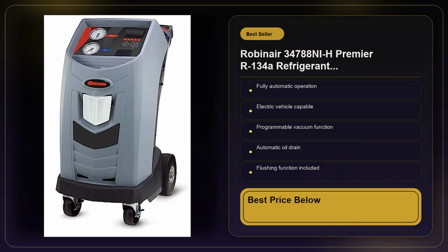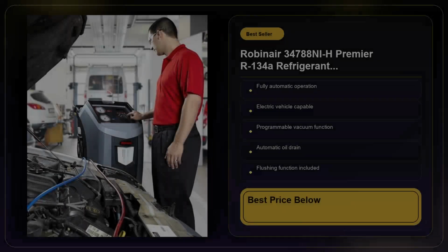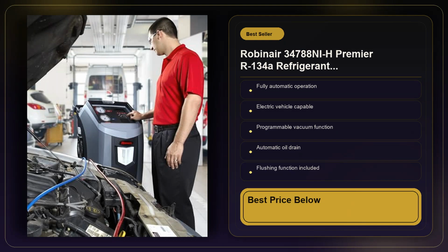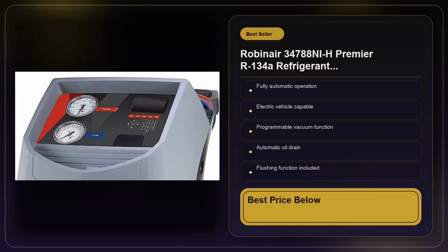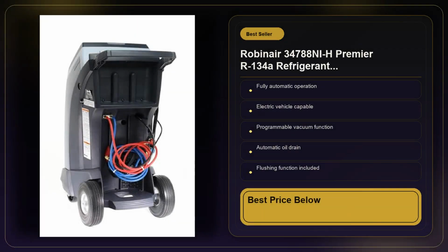The automatic oil drain is another time-saver. Oil builds up in the recovery cylinder during the pull, and manually draining it can be messy. The Robinair's internal oil separator routes that oil to a separate reservoir, so you end up with a cleaner refrigerant tank ready for reuse. On the flip side, the machine isn't without quirks.